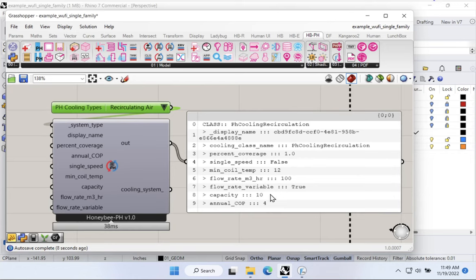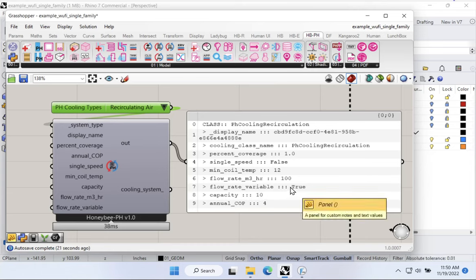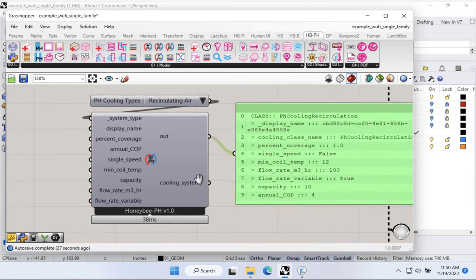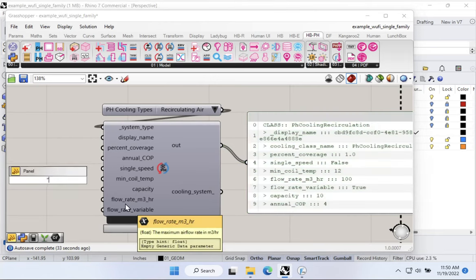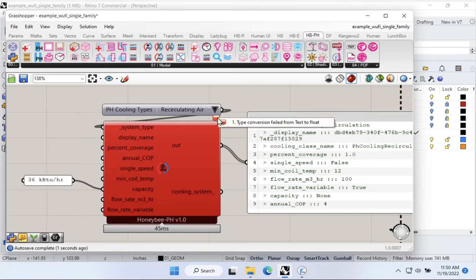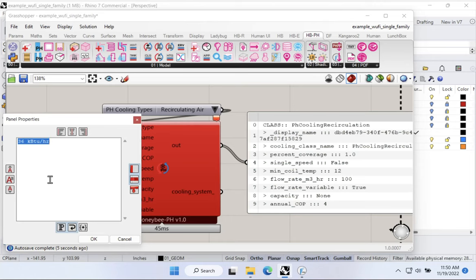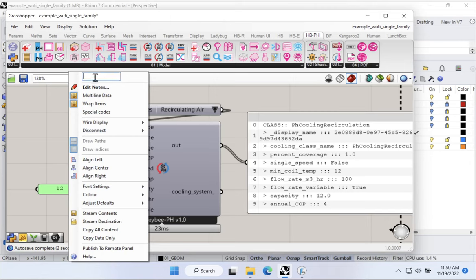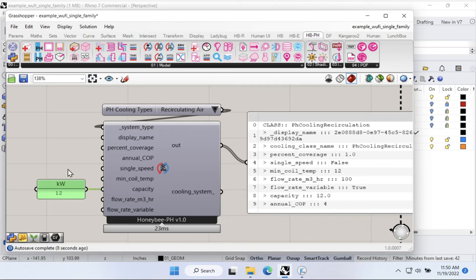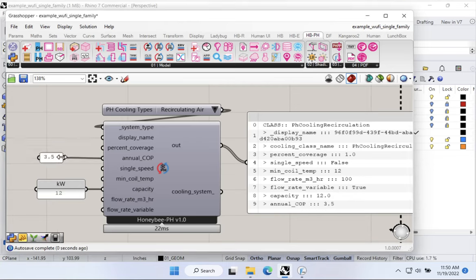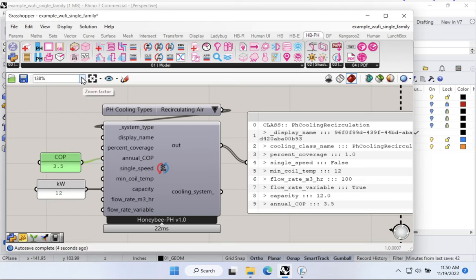Notice we get a default system out of the box with a cooling COP of 4. So notice down here we get a cooling COP of 4. And we also get some additional values being set here, a 10 kilowatts system. So what's that, like a 3-ton system, something like that. And we get some airflow rates. So we get some default rates here. Of course, we can go back and override any of those. So for a little building like this, what do you think is a 3-ton system about, right? Probably. Let's see if this works. If we said KBTU per hour, let's see, what does that translate to? So 12. Okay, there we go. So it's looking for kilowatts. So you can see the capacity flows through there. So there's our kilowatts. And we could change the COP if we felt like 4 was a little bit too high. Maybe we set that to, again, maybe 3.5 or 3.6. Whatever the number is that you would use for your system. So this will be the COP of the system there.